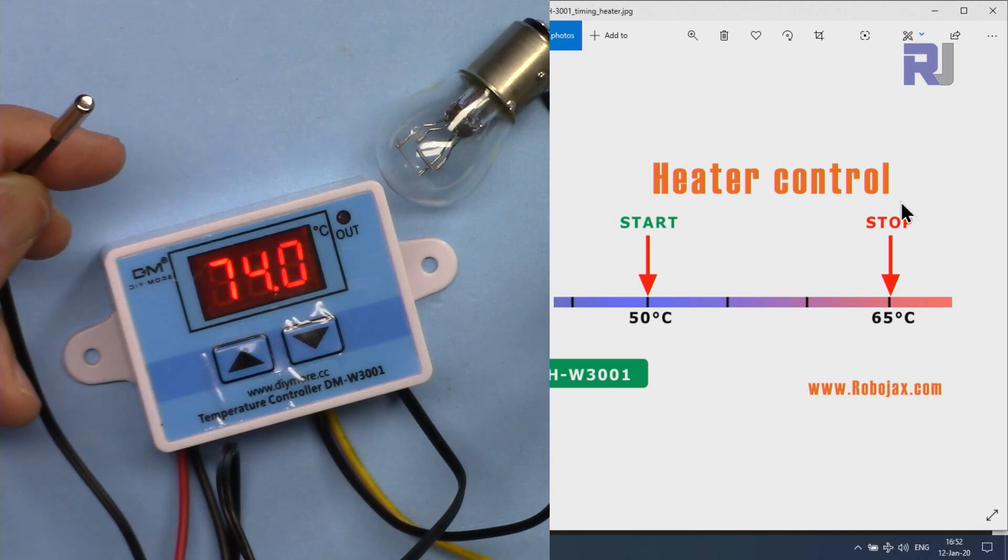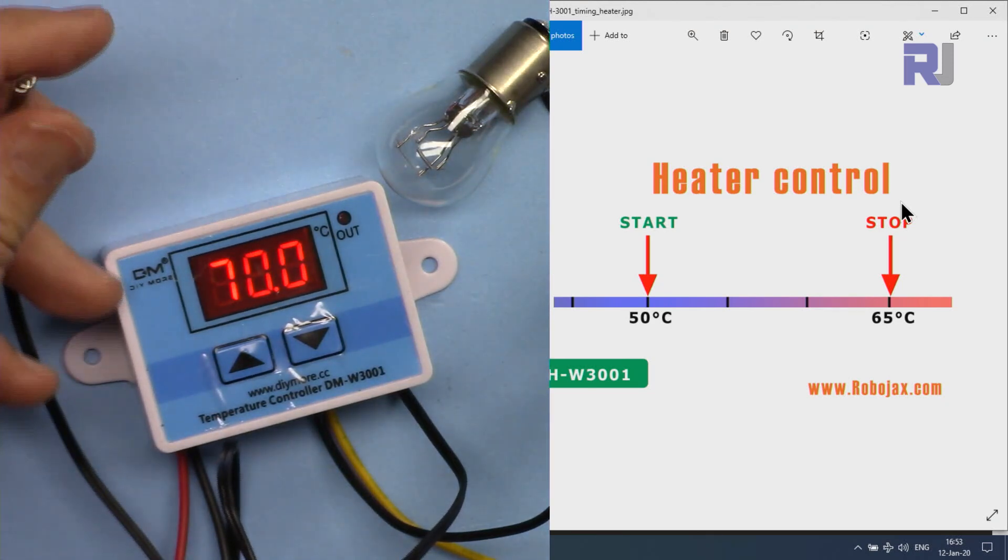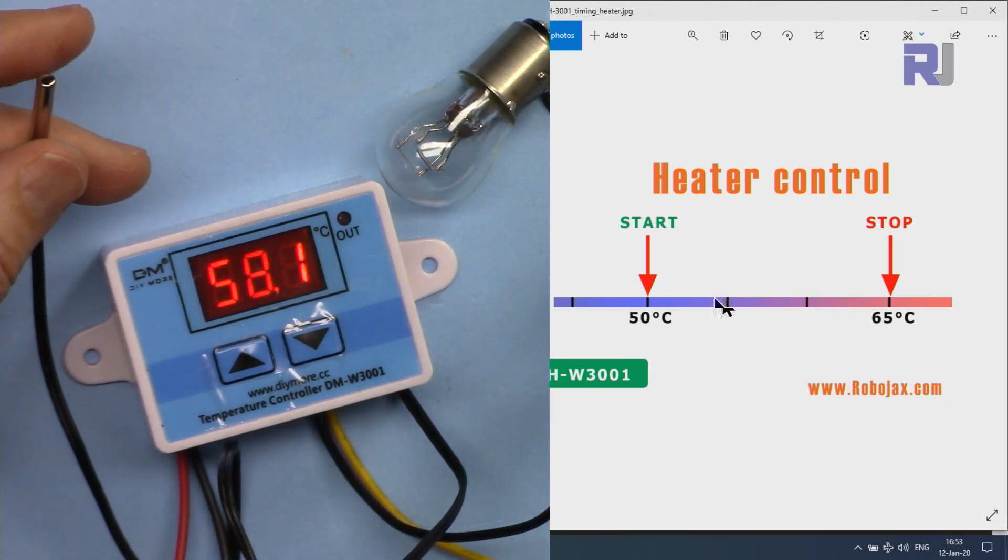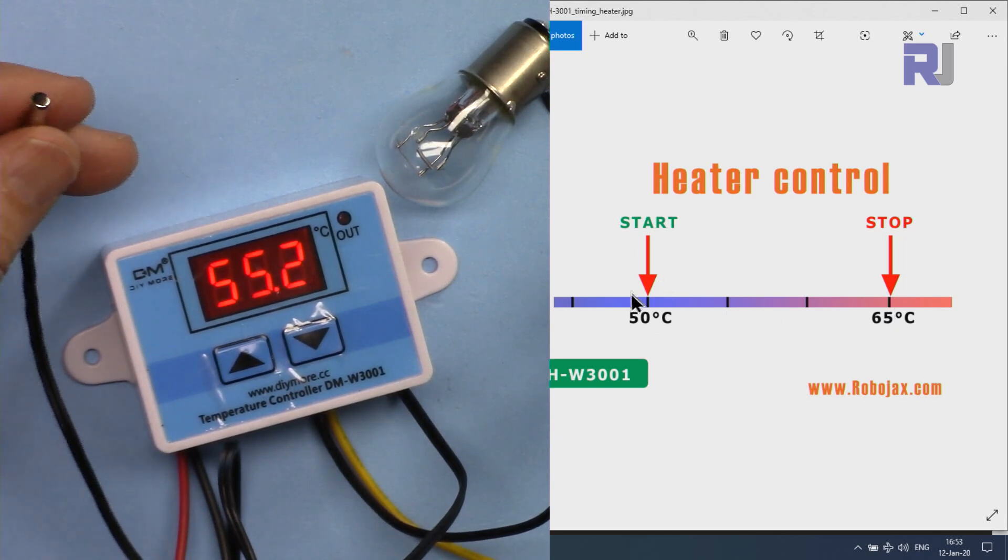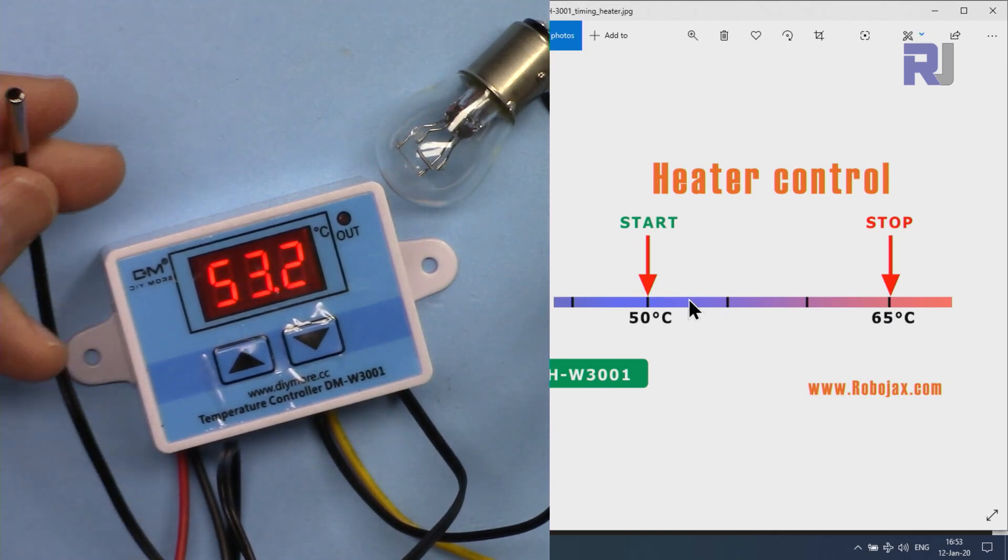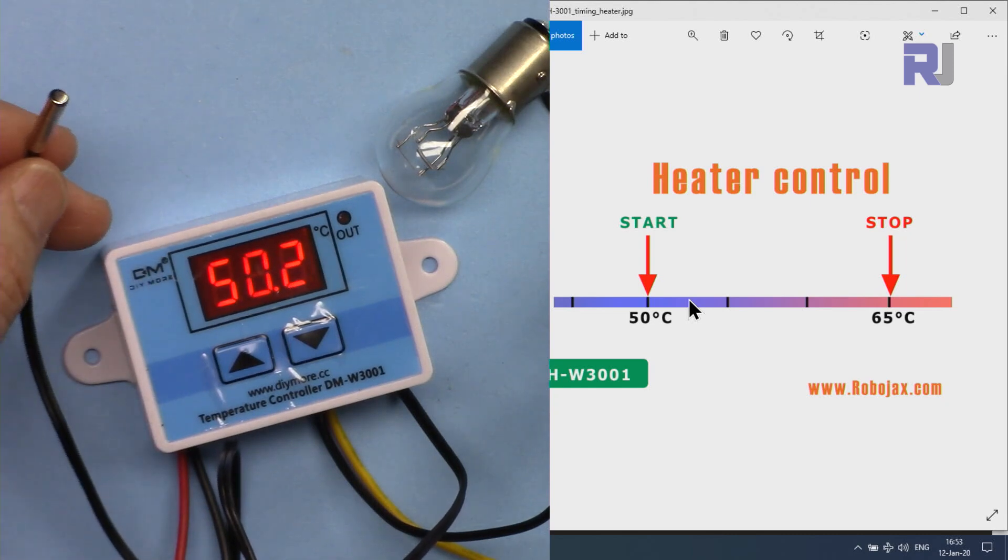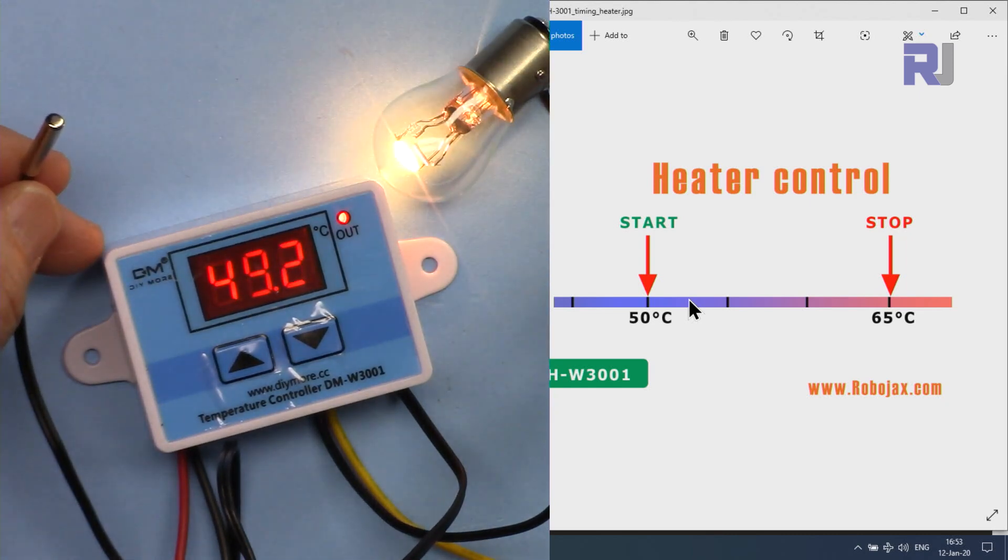So it has stopped now, and because the temperature is way above 65 it stopped. This will turn on again at 50, not at 65. When it goes down to 50 you will see it turn on. Now it reaches very quickly to 50 and it will turn on. This was how to use it as a heater.